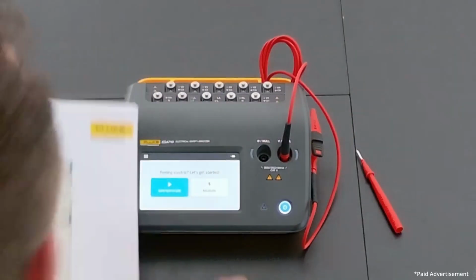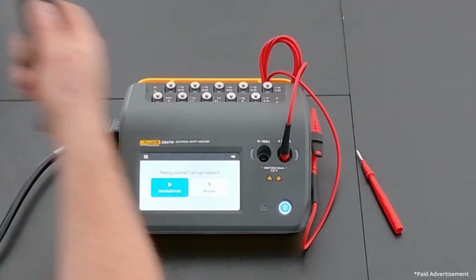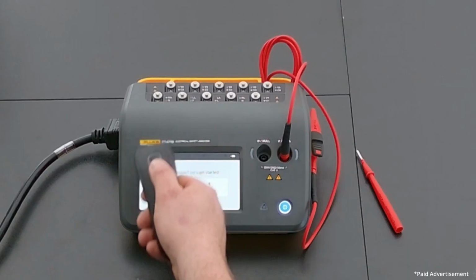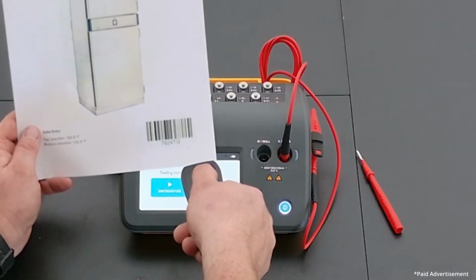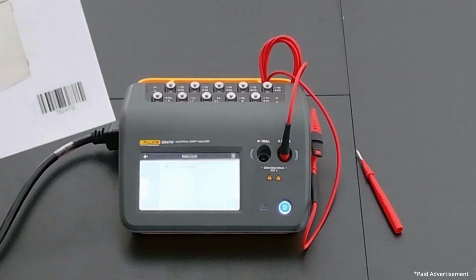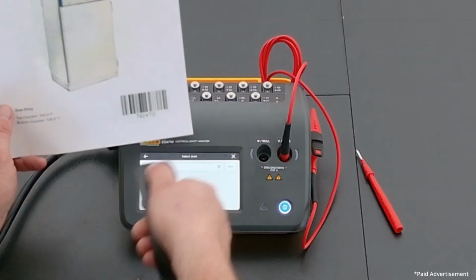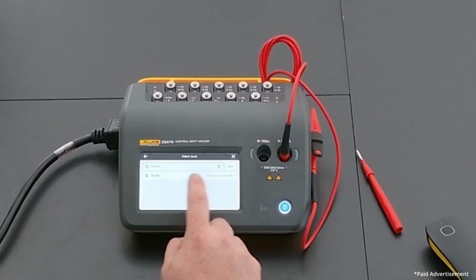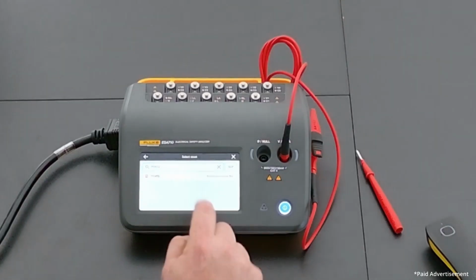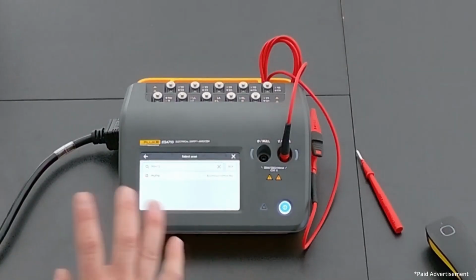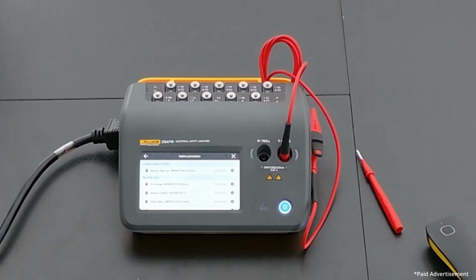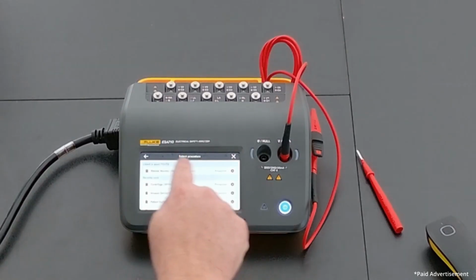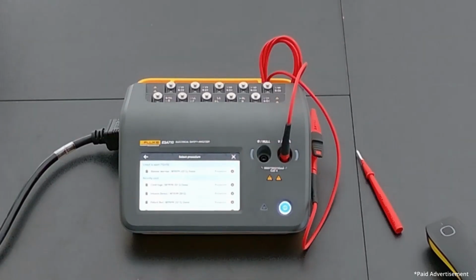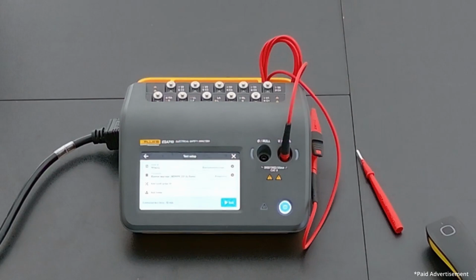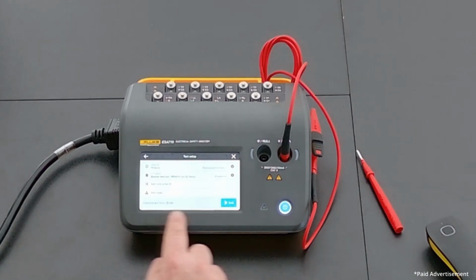So what I can do is take my barcode scanner like this and wake it up once, and scan the barcode on my asset tag. Oh, I forgot to push a button. Now I'll scan my asset tag. And what you'll notice is it's going to pull up the asset right here in my safety analyzer. Now this is where we set ourselves apart a little bit. I do this, and it pulls up my procedure for my blanket warmer right from my CMMS system. So I can go here and run my procedure. It even tells me roughly how much time it should take to do my procedure.